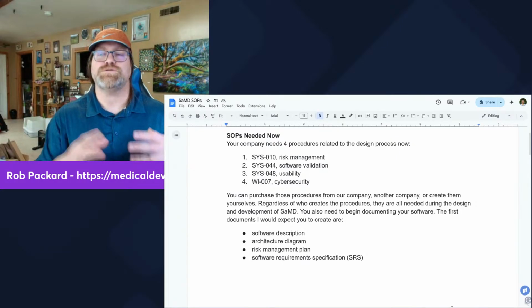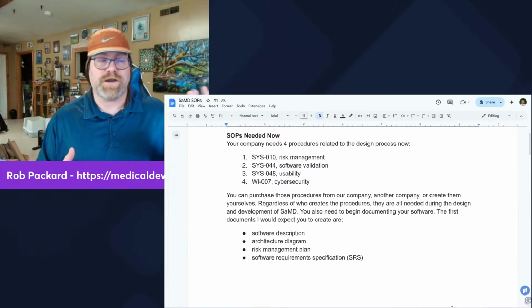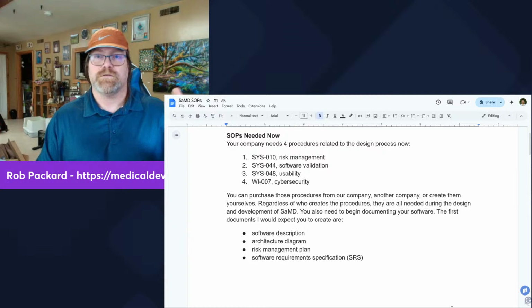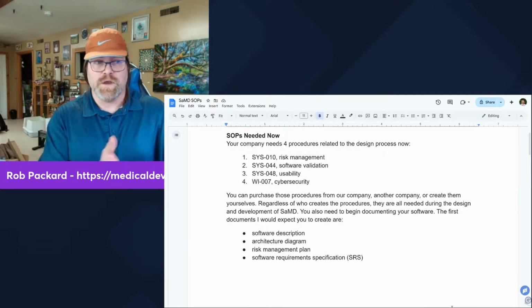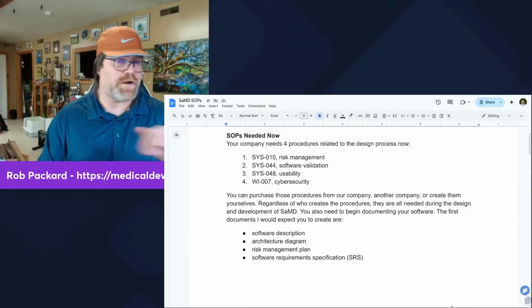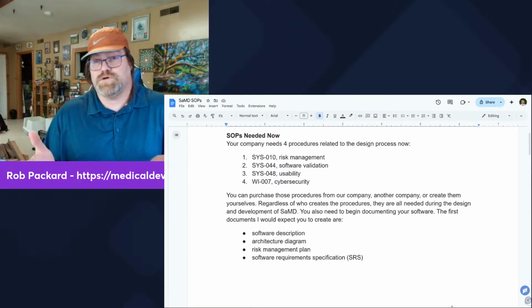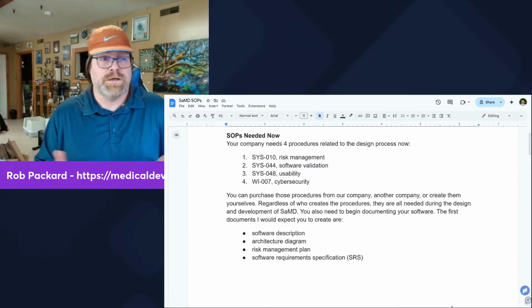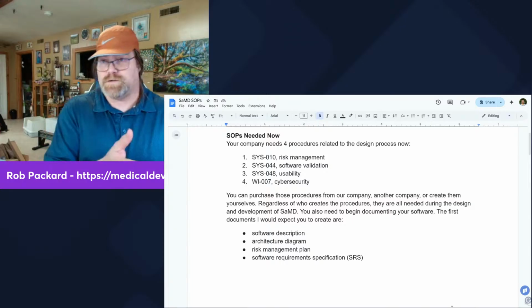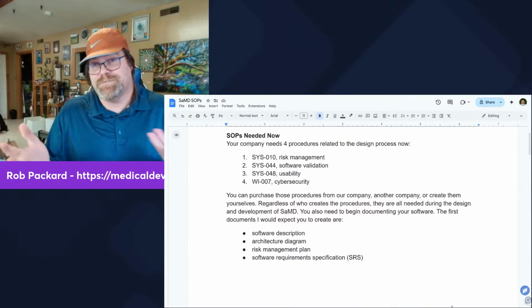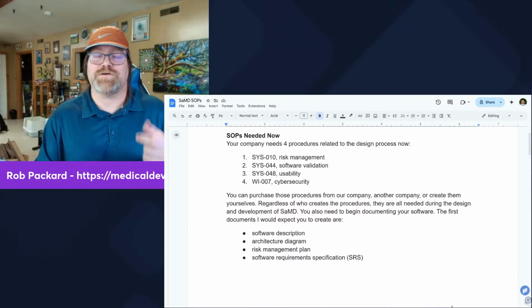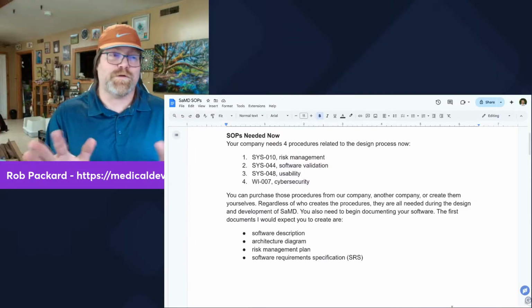But your SRS should be drafted. I mean, right out of the gate, you should be able to list the 8 minimum requirement documents, the risk controls that you have to have for cybersecurity. There are 8 risk controls they want for cybersecurity. They should all be in your SRS right out of the gate. And your software is supposed to do something. So there's a requirement. What does it do? There's a requirement. So we get 9 right out of the gate before we even think about it.